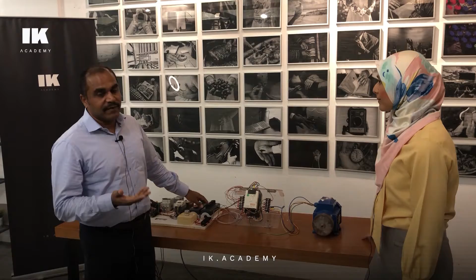So we will be able to program this variable frequency drive to run at a different speed, or to run at a reverse speed, for instance, or to stop at a certain signal. Instead of using a programmable logic controller, because we are focusing on the motor and variable frequency drive, we will simulate it by using a simple switch here. Similarly, we have a simple potentiometer here, which is used to give an analog signal. We call it analog input, which again could be from a programmable logic controller, or from a sensor. So all this can be simulated. It's a real industrial setup for a variable frequency drive and a motor, which we can simulate.